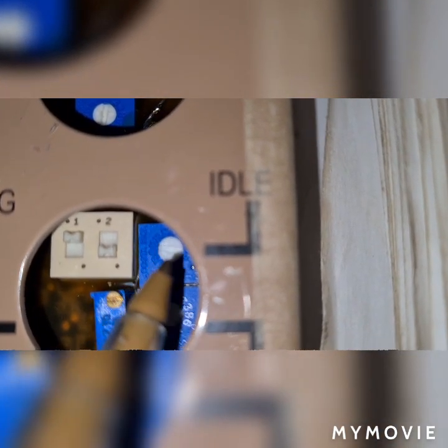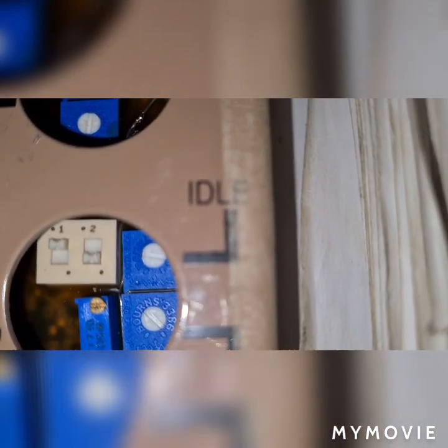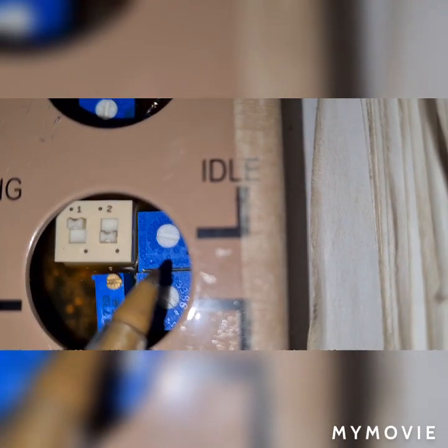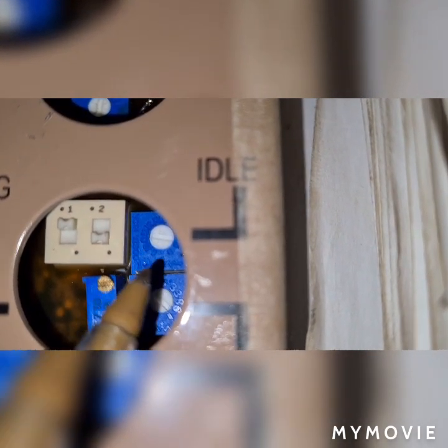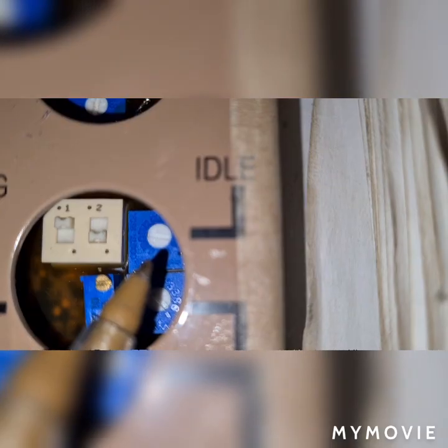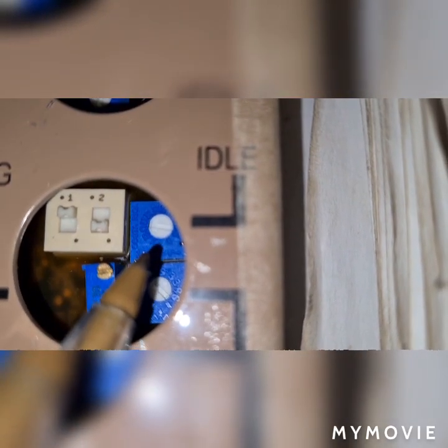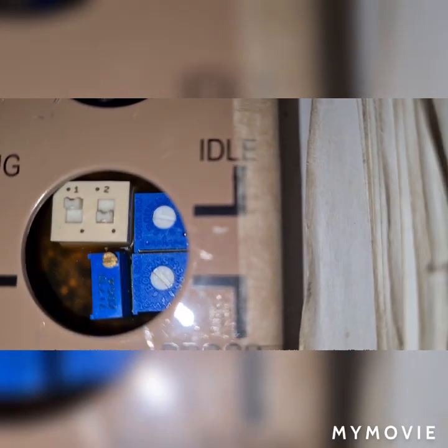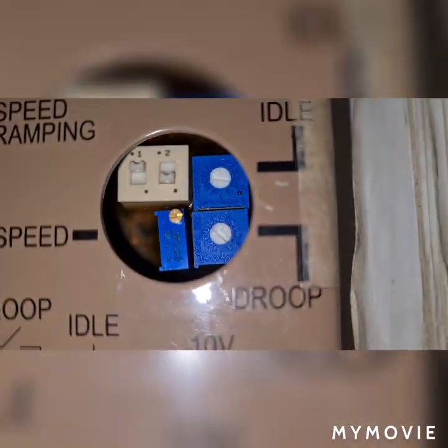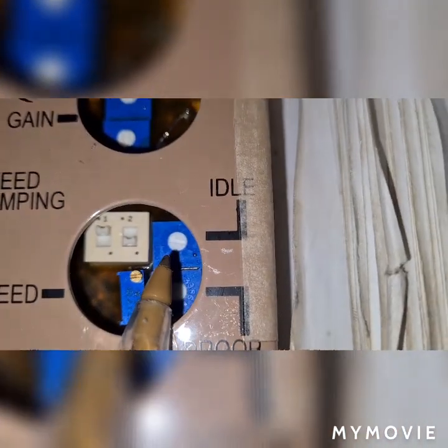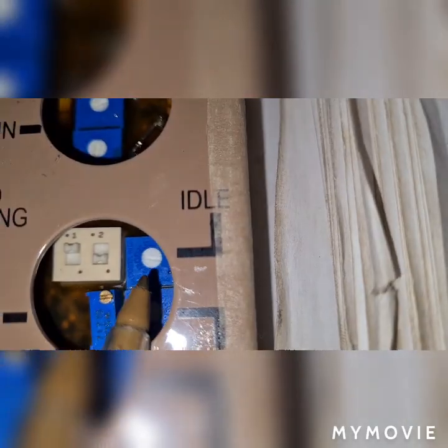Bourns 86, okay? That is idle speed, meaning you can set your idle speed. When the generator runs without load, you can also get here the rated RPM of 1800 RPM. Take note that you may get idle speed increased by rotating in a clockwise direction.